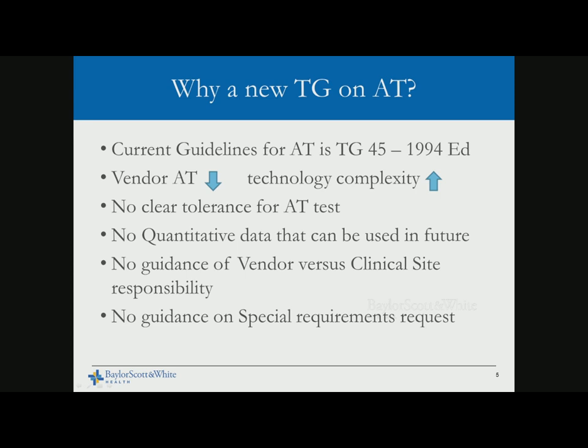So why a new TG report? We have TG report 2.10 looking at acceptance testing recommendations. The current guidelines come from TG 45, a 1994 edition, and a lot of things have changed in the last 22 years. If you look at what is happening with vendor acceptance testing, the tests and documentation are reducing while the technology and complexity are actually increasing.